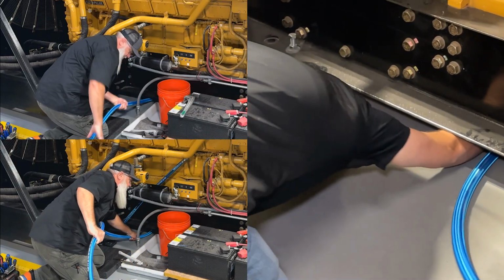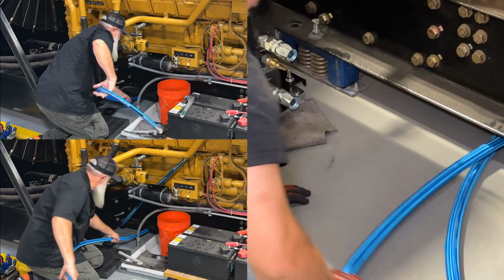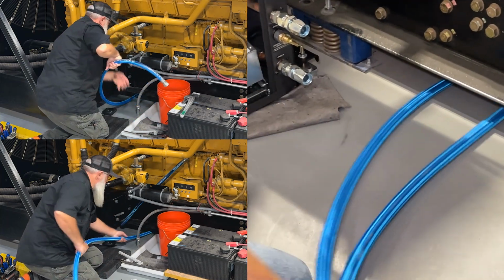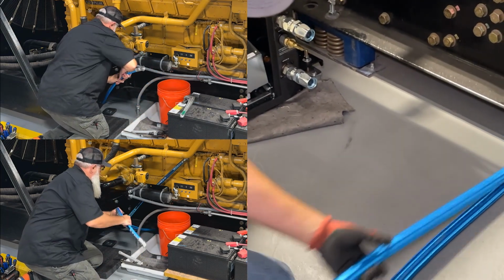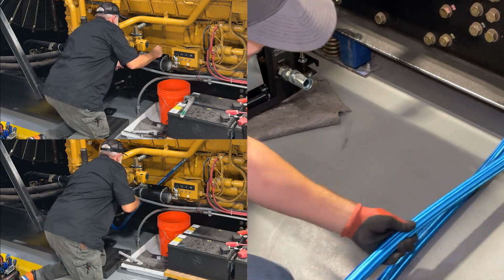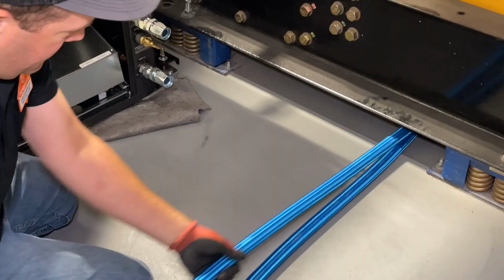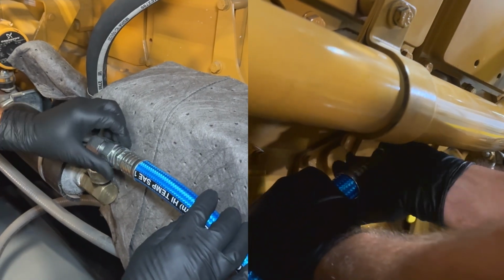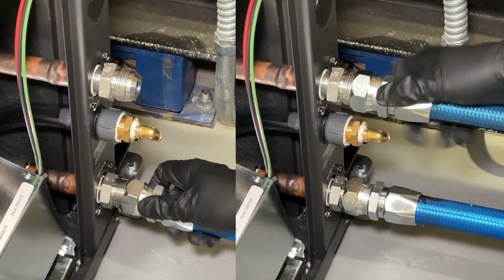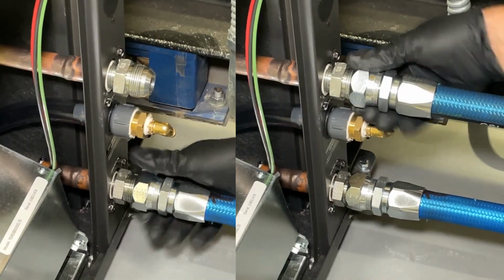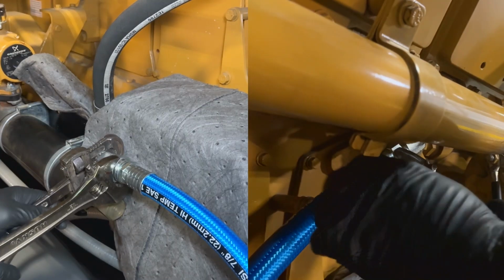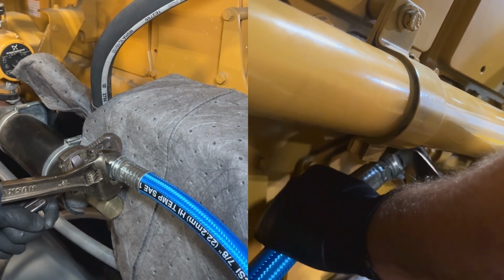Route the hoses from the existing heater side to the heat pump side. Depending on the setup, hoses can be routed under the engine through an access point in the skid or under the skid if it is elevated by vibration isolators. Hand tighten the hose fittings on each end, then secure in place with a wrench.